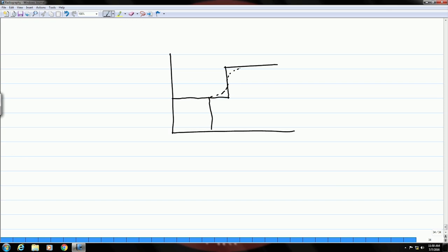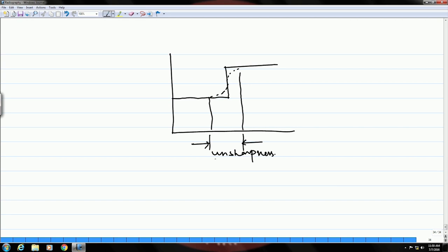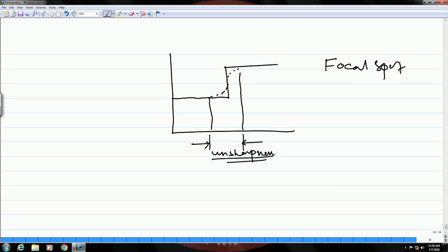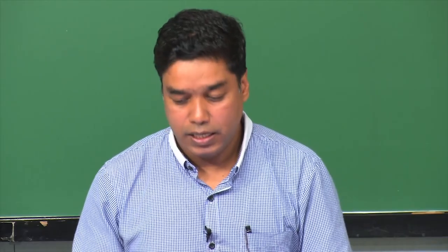You had a boundary where there was a 90-degree change, but when you see the image, you do not see that sudden change — rather it comes out as a gradual change. This inability to reproduce the boundary properly is known as the unsharpness of the image. This primarily happens due to the focal spot size of the machine.